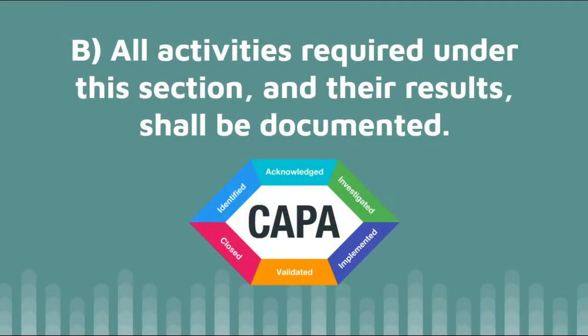For subsection B of corrective and preventative action, all activities required under this section and their results shall be documented. This means that every single bit of manufacturing, which includes processing, operations, investigation of nonconformities, and identifying of such issues, the validation of the processes, and the implementation of such issues, must all be recorded, must be documented, and saved for management.